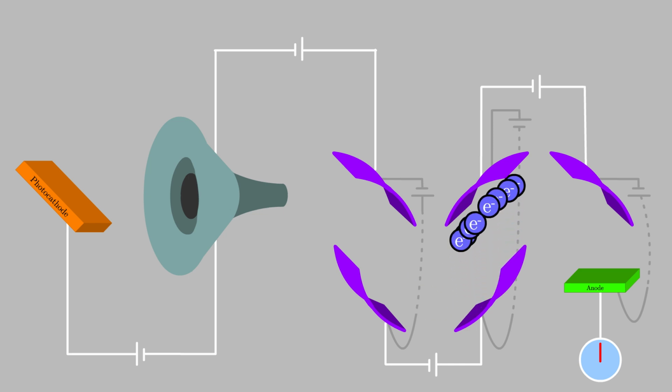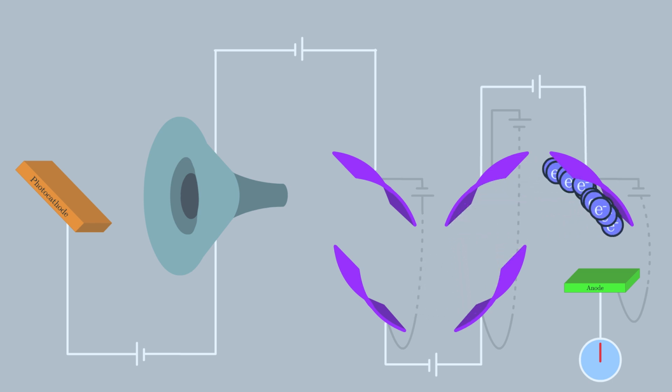Of course, the environment for all of this is crucial. The tube must be a strict vacuum because electrons are traveling inside, and we don't want them colliding with air molecules and losing energy. So, we seal everything inside a glass tube. We must also choose the correct type of glass window that can transmit the specific incident photon frequency. If the glass blocks the photon, the photocathode can't eject an electron, and we measure nothing. So, this is basically how a photomultiplier tube works.